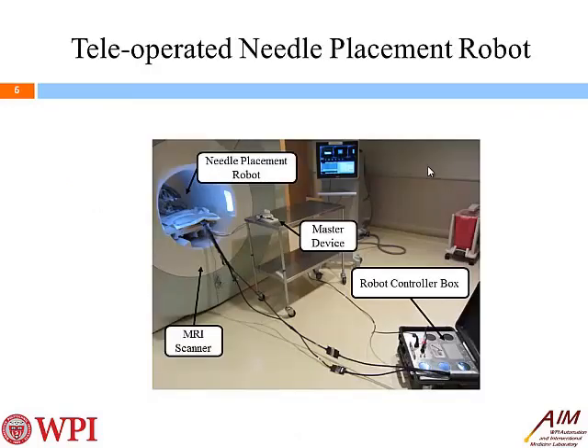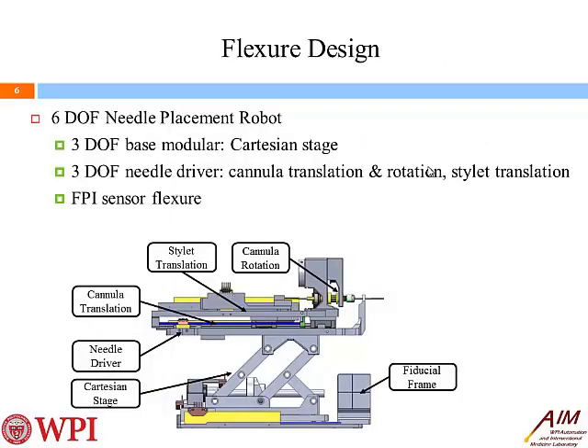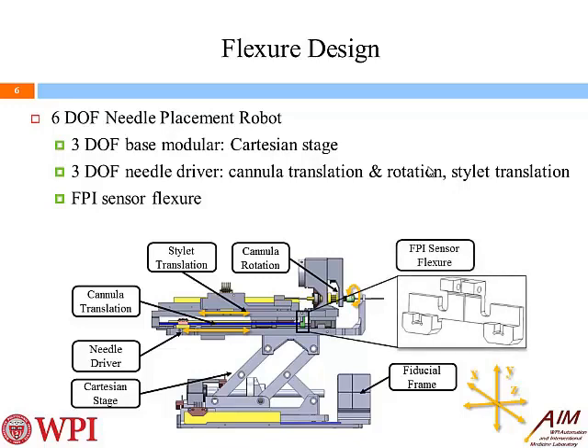The FPI fiber sensor is designed to be integrated into our teleoperated needle placement robot. The robot consists of a robot controller box, a master device, and a needle placement robot. This figure shows the system set up in an MRI scanner here. The 6-DOF needle placement robot consists of a 3-DOF base module, which is a decoupled XYZ Cartesian stage, and a 3-DOF needle driver, which can drive the cannula translation, cannula rotation, and stylet translation. To register the robot to the MR scanner and the patient in the patient coordinate system, a fiducial frame is firmly attached to the base of the robot, and the flexure is designed to attach the FPI sensor and also constrain the motor drive rods to detect the needle insertion force.